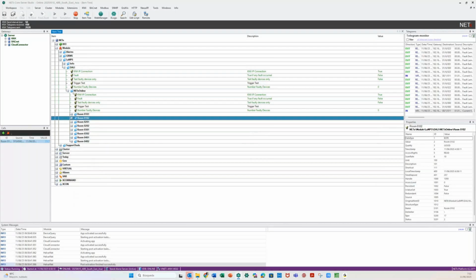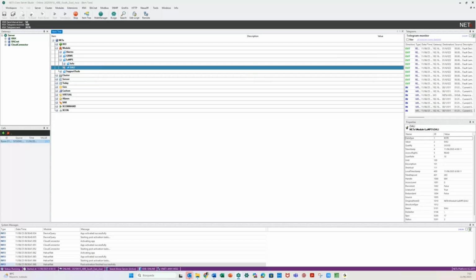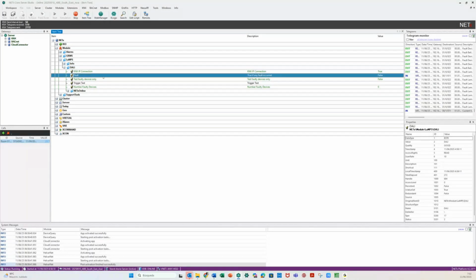That is very interesting. And then the second and third approaches. You can trigger alarms if you have any issue, you know how to do an alarm. So maybe this item has to be monitored, and then send me an email if you have any issue in DALI. Maybe this is not good because you have 2,000 ballasts, you will get emails every hour because sometimes it's happening. But I think it's more interesting to get a report. So this is the second approach.